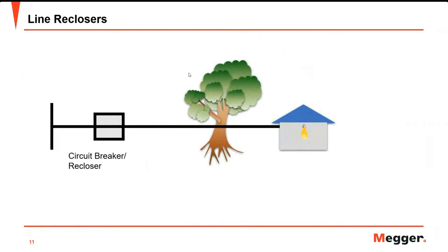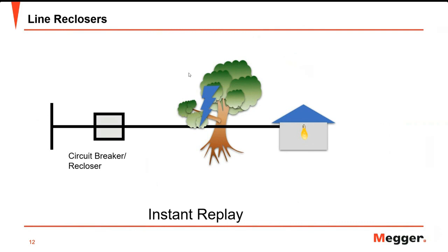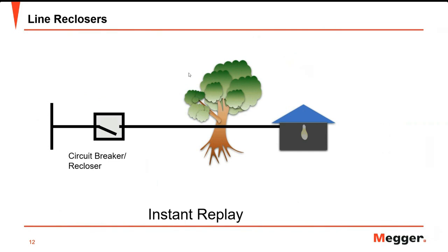Let's review the process of auto-reclosing. The wind blows a tree branch towards the feeder conductors, which causes a line-to-ground fault. The relay senses the fault and trips the breaker. The wind passes and the branch is cleared from the conductors. After a certain time delay — what we call the dead time — the relay issues a close command to the breaker and customer power is restored.